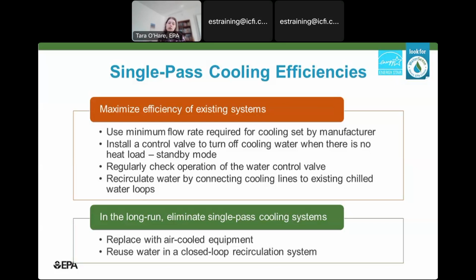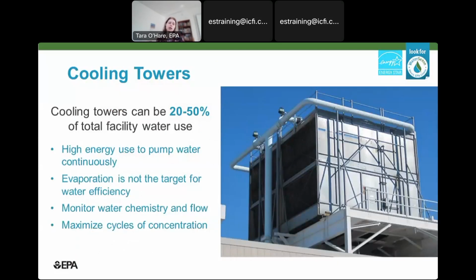In the long run, you want to eliminate single pass cooling as much as you possibly can, because it is such a huge waste. And you want to replace it with air-cooled equipment. A lot of those are Energy Star labeled, so that's something to look for. And you can also reuse water in a closed loop recirculating system if you find that that makes sense for your facility. So cooling towers can be really significant. Not every building has them, but if it does, it can be 20 to 50% of your total water use. And it's a really high energy using area because water is pumped through the system continuously.